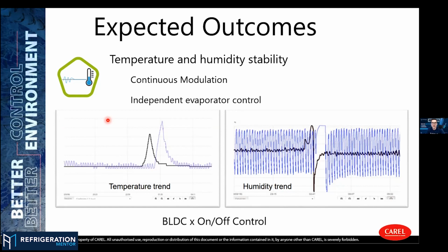I do have a quick question for you. In regards to the EV opening to balance that pressure, because I know you said you can do it through the oil side as well, are you worried about liquid flood back for that time? Generally speaking, when we have this kind of size of unit, it is not a big problem to just adjust the pressure, because when the compressor stops, it could stop by just stopping the compressor or doing pump down. During the pump down procedure, you make a big delta P. So injecting a little bit of refrigerant on the evaporator side just makes the pressure rise a little bit and makes the compressor start a little more smoothly. It's not a matter of being open for a lot of time with the compressor off. It's just for a few seconds to make these adjustments on the pressure. So we are not worried, because also the charge is very low.